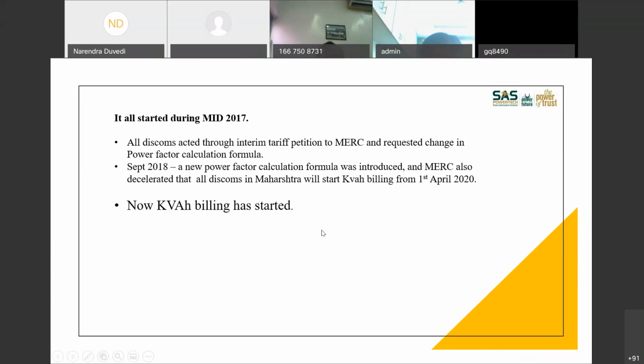See, what happened was, the earlier HT meters which were installed in industry in Maharashtra were programmed to read leading power factor as unity. So it was not possible to get an exact kVAh figure from the meter and start kVAh billing immediately. That's why, as we all know, in September 2018 our power factor formula was revised, with kVARh lag plus lead in the denominator, and that was somewhere close to kVAh billing.